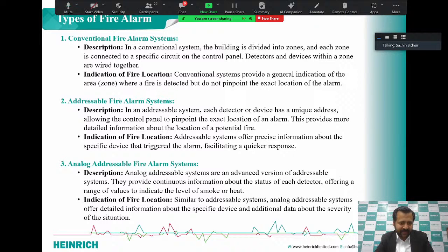So the analog addressable fire alarm system is an advanced version of the addressable system, which provides continuous information about the status of the detectors and offers a range of values for the level of smoke or heat. In the addressable system, even if dust or other particles, not smoke particles, came, they used to create a false alarm. Now, with the help of other systems, we have a particular range of particles which are in smoke. With the help of those smoke particles, we can get rid of the false alarms that used to come before. Now the alarm will only come if the fire is real.